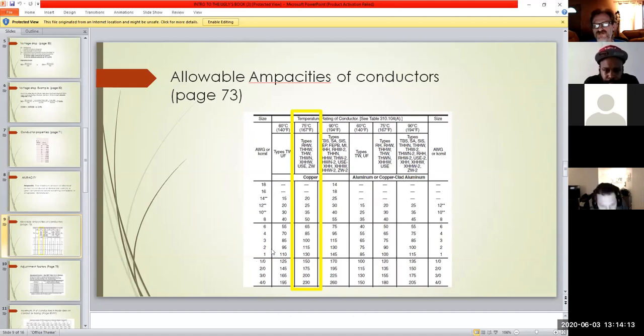Then we get down to the really giganormous sizes, 1-aught, 2-aught, 3-aught, 4-aught. These are usually the ones running outside, like what Ameren or ComEd brings into your house, down the mast to your service. That's pretty much where these really large wire sizes end. 4-aught is up to 195 amps. So if I'm running a 200 amp service, I'm bringing in the big boys, but it's going to end basically coming into the service panel. From that point, I start running out with smaller wires depending on what size breaker I have. This is pretty much a golden rule - we can match it up.